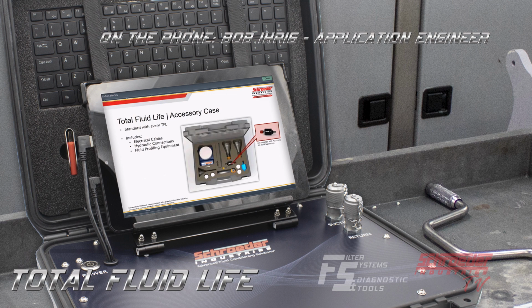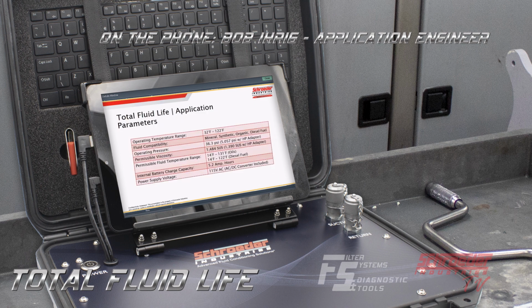But I recommend purchasing that anyways, because as you will see here in the application parameters, operating pressure, which should actually be inlet pressure, is only capable of handling up to 36 psi. With the high pressure adapter, we can process or reduce up to 5,000 psi down to an acceptable inlet pressure.